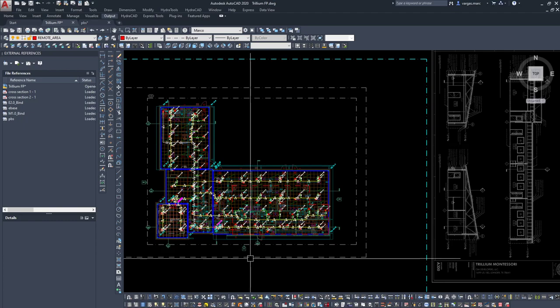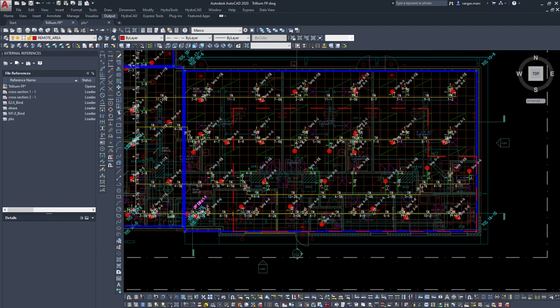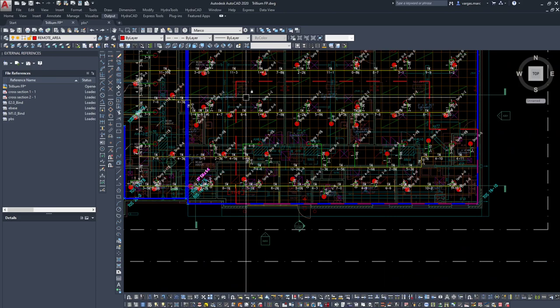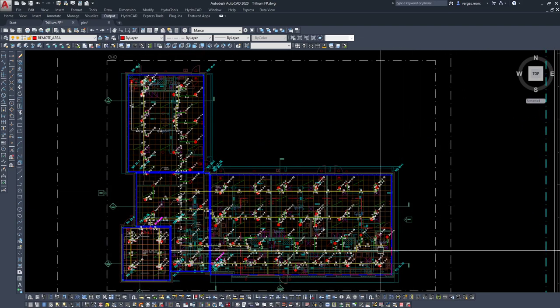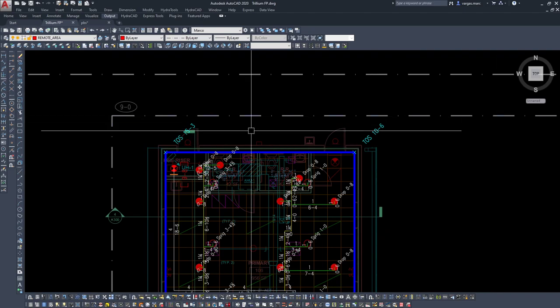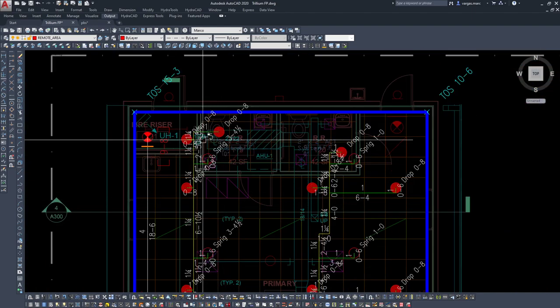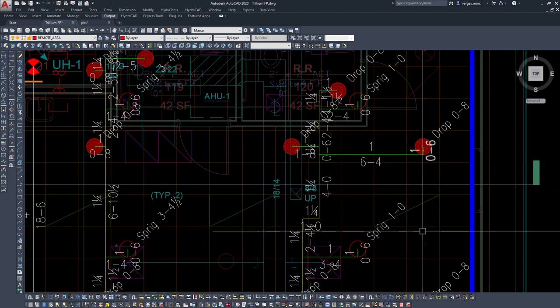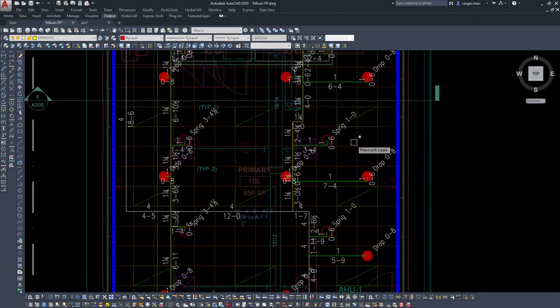Welcome back. We're still working on the small church. I laid out my remote area and decided the best sprinklers to calc for this are going to be the uprights above the ceiling. I'm going to use a full 1500 square feet for the remote area. I like to run auto calc just to the top of the riser and then manually input the underground. I need to place riser nipples on the sprinklers going to the center of the ceiling tiles and also add caps to the ends of the branch lines — I'll do that real quick with QC for quick cap.